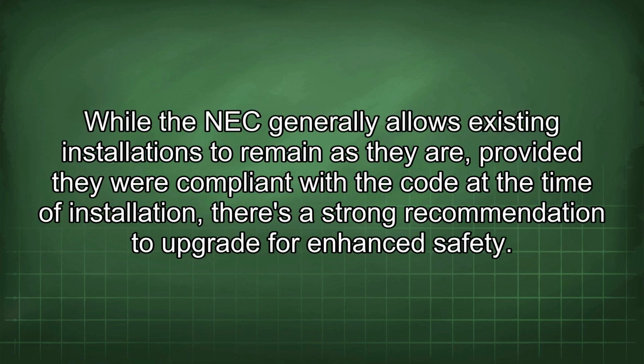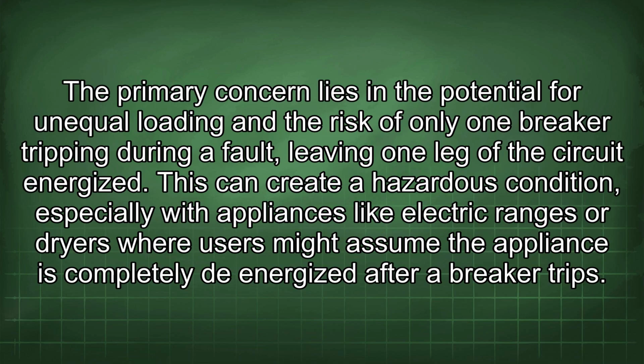While the NEC generally allows existing installations to remain as they are, provided they were compliant with the code at the time of installation, there's a strong recommendation to upgrade for enhanced safety. The primary concern lies in the potential for unequal loading and the risk of only one breaker tripping during a fault, leaving one leg of the circuit energized. This can create a hazardous condition, especially with appliances like electric ranges or dryers, where users might assume the appliance is completely de-energized after a breaker trips.